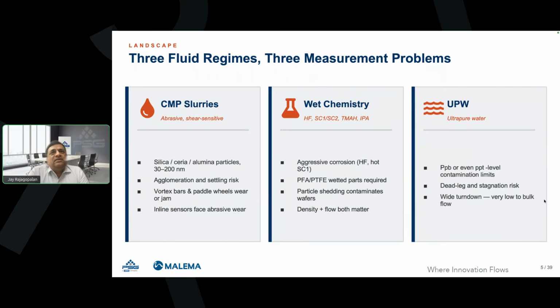Wet chemistry, here the concern is that the chemistries are extremely aggressive in nature, extremely corrosive. Hydrofluoric acid, for example, hot SC1 and SC2 type of chemistries, formulations, and also very toxic TMAH type of developer chemistries, IPA, etc., are quite difficult to handle. PTFE and PFA wetted parts are usually preferred. Particle shedding and contamination coming from the flow devices are extremely concerning. And if you have to maintain high purity there, density and flow also matter in this space because you're really formulating chemistries, mixing different chemistries, etc.